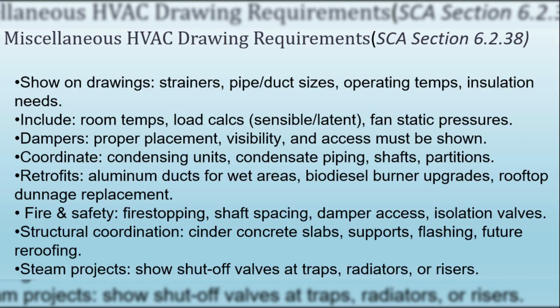There are also important coordination items: location of condensing units, condensate piping, fuel oil pipe shafts, shaft sizing, and avoiding ductwork over partitions. Dampers, isolation valves, condensate lines, and combustion air damper visibility are all details that must be called out. Some very specific requirements exist for older schools and retrofit projects, such as aluminum ductwork for wet areas, replacement of rooftop dunnage, insulation standards for combustion air ducts, and proper fire and smoke damper access.